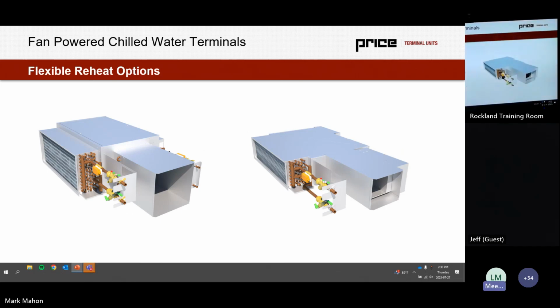I like to talk a little bit about the flexibility of the reheat options. I know I referred to this before. When we think about a historical hot water coil on the discharge of a terminal unit, they were designed for 180 to 140 degrees of entering water. That's how their circuitry was laid out. That's how their sizing, fins per inch are all laid out. And that would allow for a 1-row coil for 180 water, 2-row coils for 140 degree water. That's what we see most people specify and utilize most of the time for reheat coils.